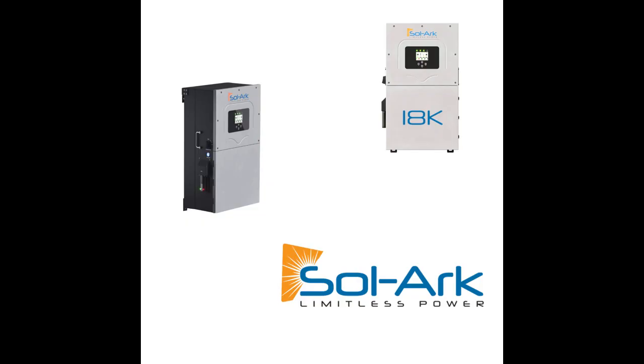Really, again, we're just going to recap the differences here between the 15K and the 18K. So again, the 15K, which has been our flagship, which we built off previous technology, is 15K from PV, but really only 12K from battery. And 12 kilowatts is a conservative value. If you do amperage times voltage, you get closer to around 14 kilowatts continuous, but on the low end of the battery voltage, around 48 volts, you're still going to get that 12 kilowatt output.